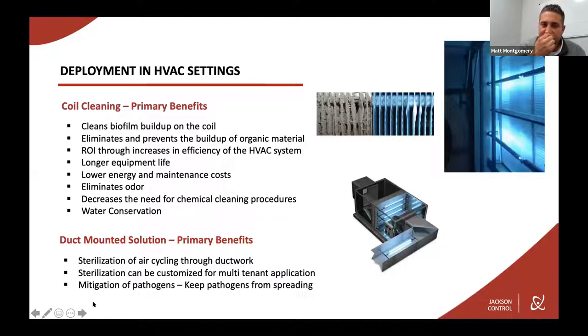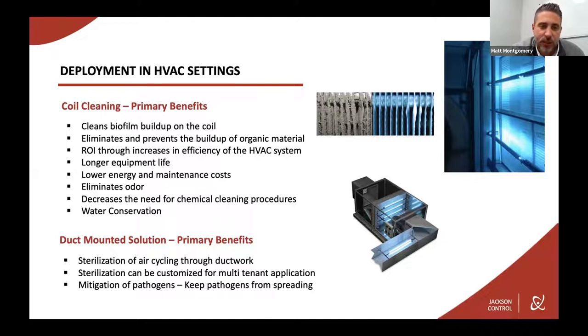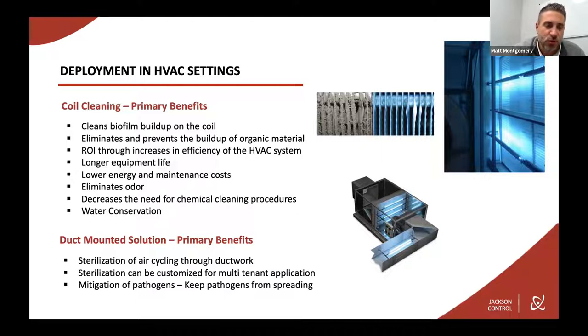Talking about UVC deployment in HVAC settings, we'll focus on two of the most common applications. The first is coil cleaning, which is what you primarily see UVC light used for in HVAC settings. The benefits include cleaning the biofilm buildup around the coil — biofilm is mold and dust that accumulates over time. It eliminates organic material buildup, provides measurable ROI through HVAC efficiency increases. A biofilm buildup of just 0.006 of an inch will lower efficiency by 16%. You'll get longer equipment life, lower energy and maintenance costs, odor elimination, and decreased need for chemical cleaning. A notable benefit is water conservation — water condensate coming down the coil becomes distilled water once UVC is introduced, which can be reused as cooling tower makeup water.